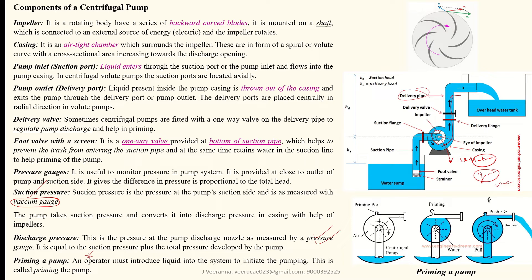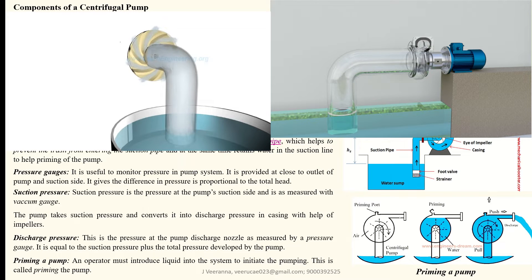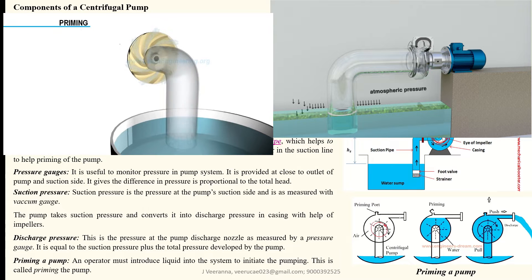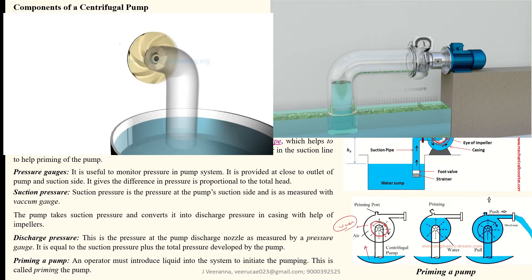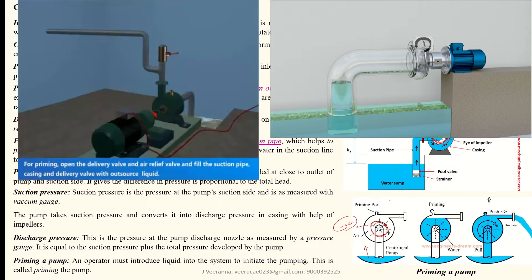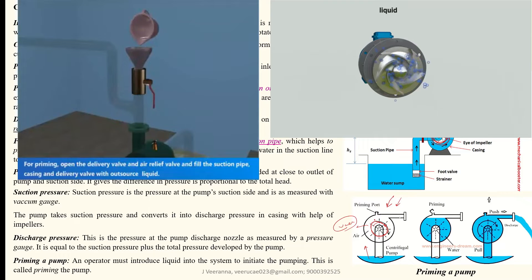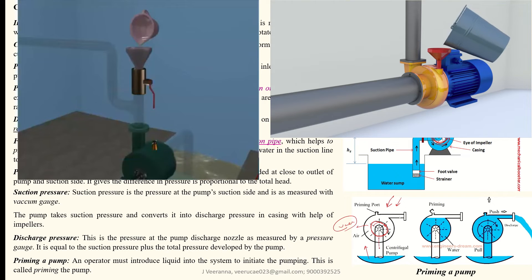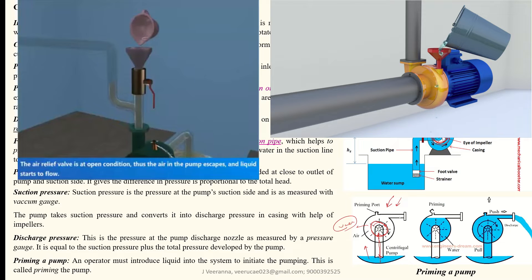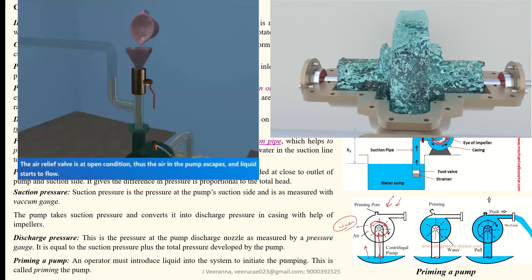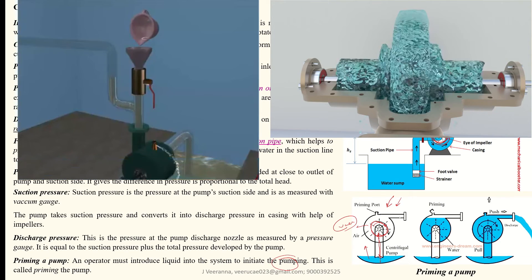Pump priming is very important. When there is no water in the impeller, the impeller rotates and a vacuum is created, but the water will not move into the impeller. So we must manually add water to the impeller using special provisions to ensure continuous flow from the source to the impeller. The operator must introduce liquid into the system to initiate pumping — this is called pump priming.